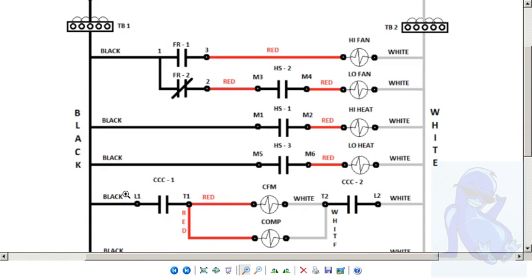Very, very laggy. So we have L1 to the cooling contactor and terminal 1 for the condenser fan motor. And in here too you'd have a capacitor wired in, but it's not going to show all that. Here's your condenser fan motor, and that's going to leg 2, and we are breaking leg 2 through the contactor as well. You don't have to.